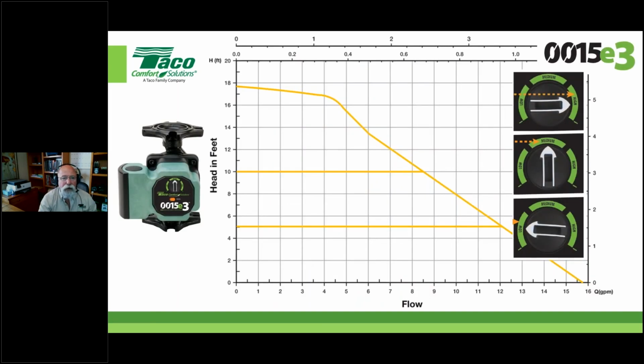Well, let's take a look at it, right? You can see here that we've got low, which is a setting of 5 foot of head under a constant pressure type operating mode. Now, I gave you a caveat when we started here that this is not really the right mode to use, but it works fine as long as you're not anticipating this pump speeding up or slowing down, because it's going to find the resistance of the near boiler piping and the boiler's heat exchanger, and it's going to find its happy spot, and that's where it's going to stay every time it turns on, give or take a little fluid differences in viscosity, right? But it's very slight.